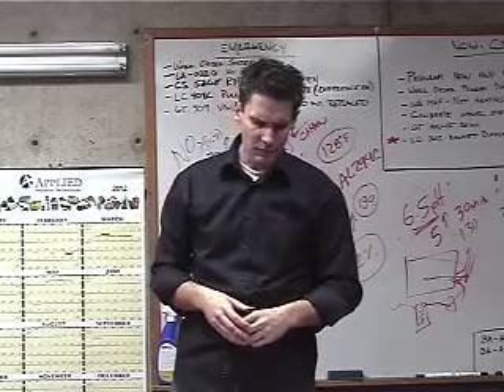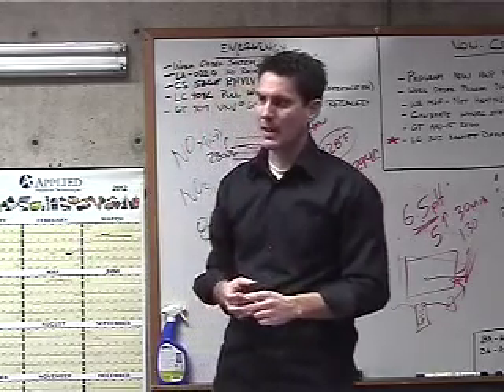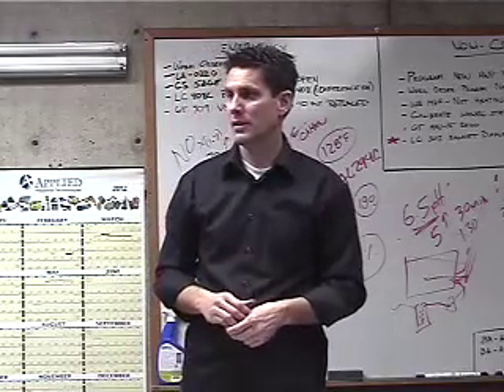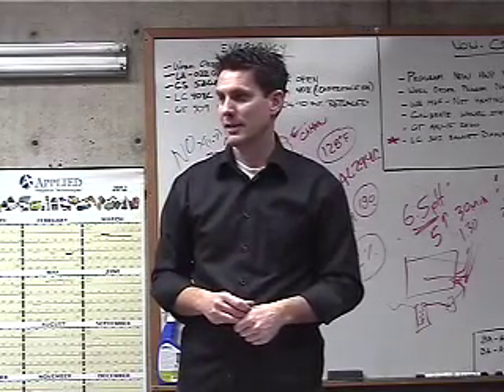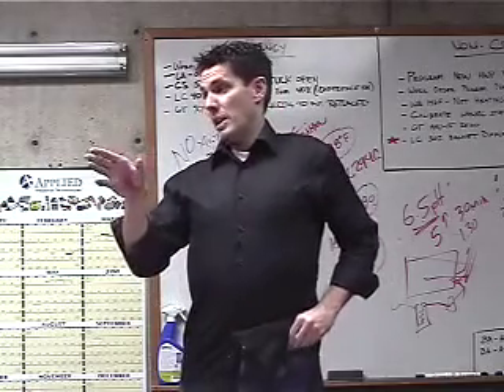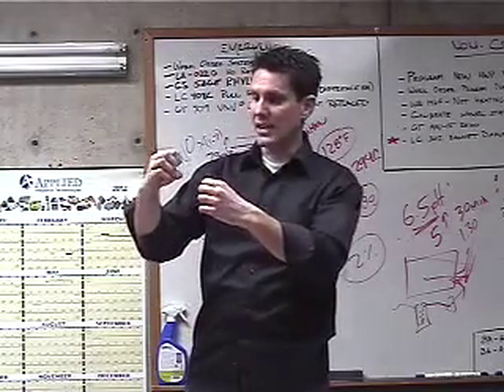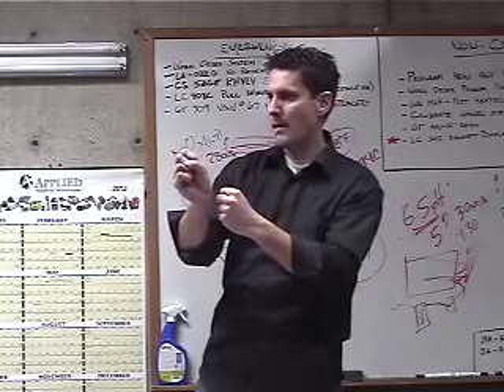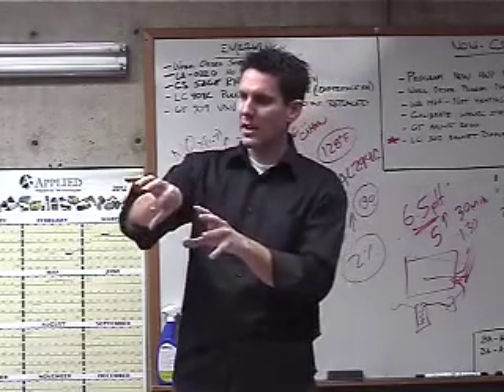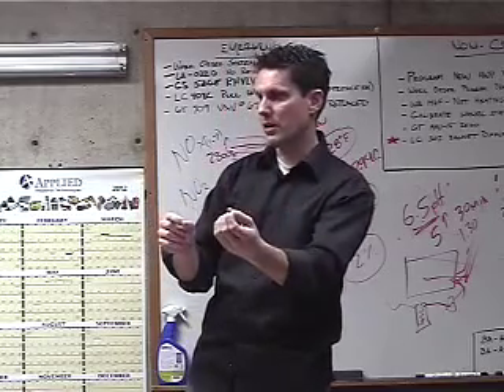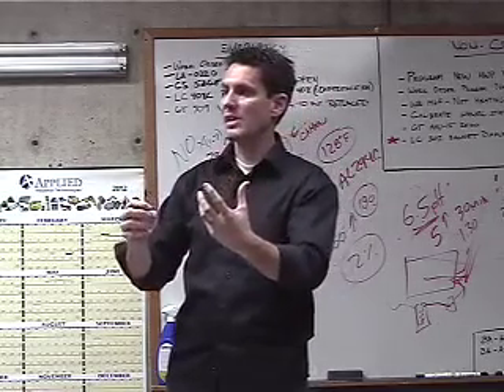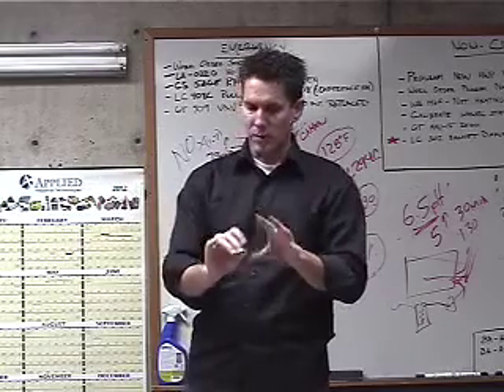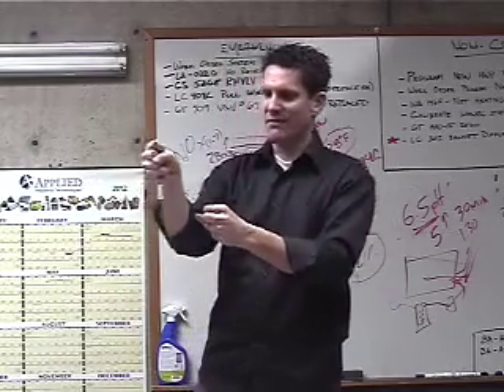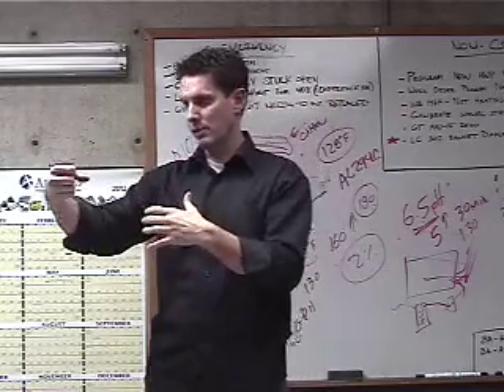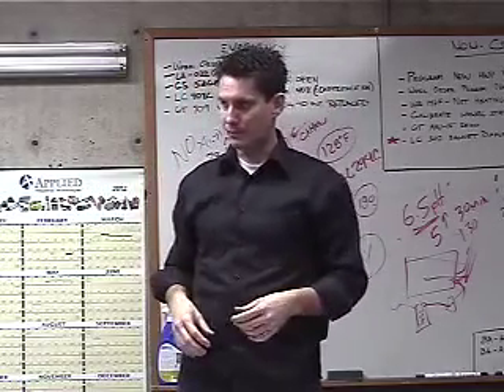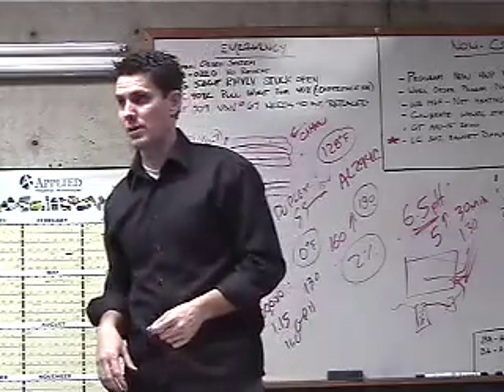I think so. Okay. But what if that outside air damper is blowing directly into the vent, won't that adjust? And see, no, it won't, because what we've set it up to is just a position. It's the same controller, but it's sending a 4 to 20 milliamp signal not based on the oxygen that it's reading. It's sending a signal based on the position where the valve needs to sit. So as we program it, at low fire it needs to be at maybe 10% open. At high fire it needs to be at 98% open. So you might get more air with more pressure. Yes, you will get more air with more pressure.